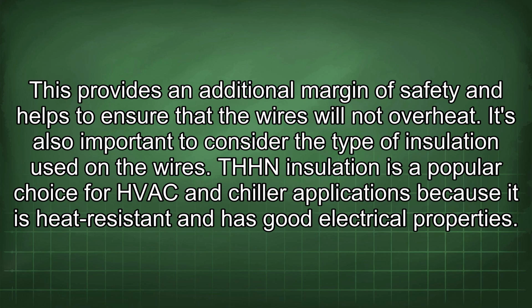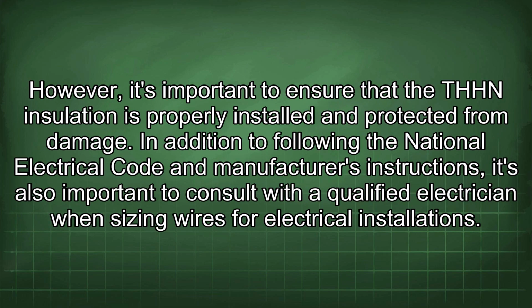It's also important to consider the type of insulation used in the wires. THHN insulation is a popular choice for HVAC and chiller applications because it is heat resistant and has good electrical properties. However, it's important to ensure that the THHN insulation is properly installed and protected from damage. In addition to following the National Electrical Code and manufacturer's instructions, it's also important to consult with a qualified electrician when sizing wires for electrical installations.